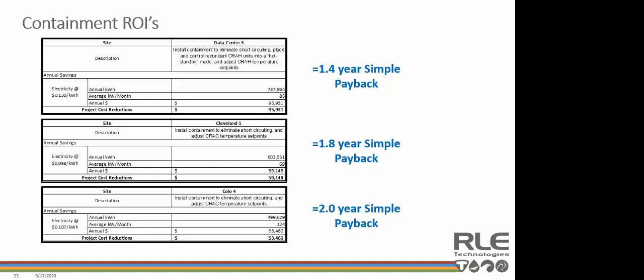The examples on this page really show savings summaries of data centers where a detailed engineering study was conducted. These data centers were monitored for individual cooling unit and chiller plant baseline energy consumption, and then calculated savings were determined by the effects of our proposed changes, which in all three cases really came down to installing a custom cold aisle containment solution, which would then enable the customer to make significant cooling unit set point changes, and in one case, place redundant cooling units in hot standby. The calculations that we put together were very detailed. Each of these studies was done over a period of months, and the actual engineering studies themselves were between 50 to, I'd say, close to 100 pages.